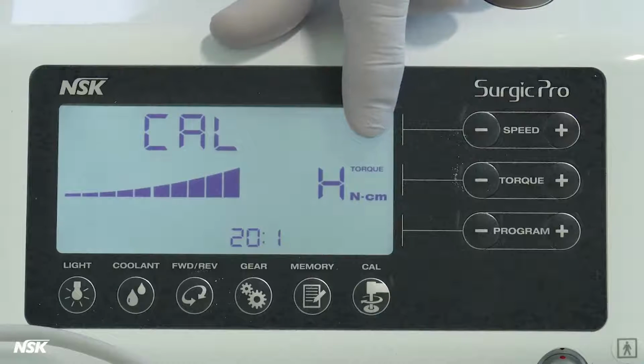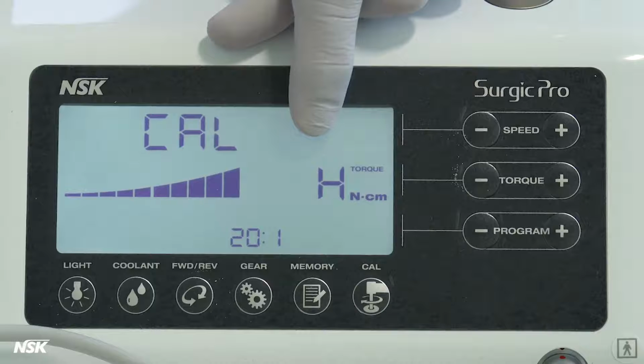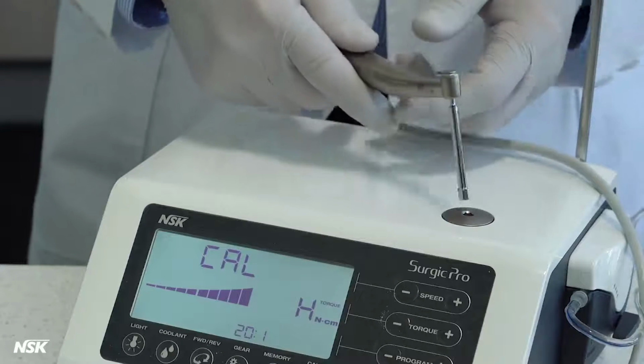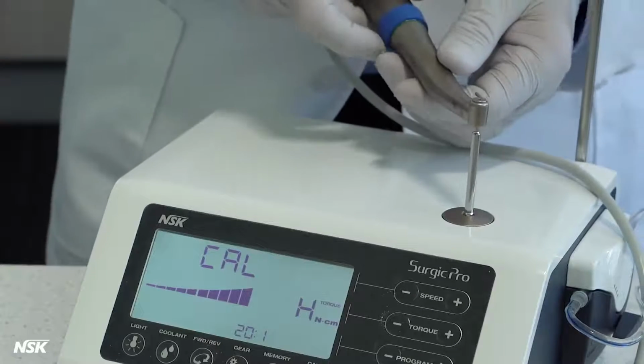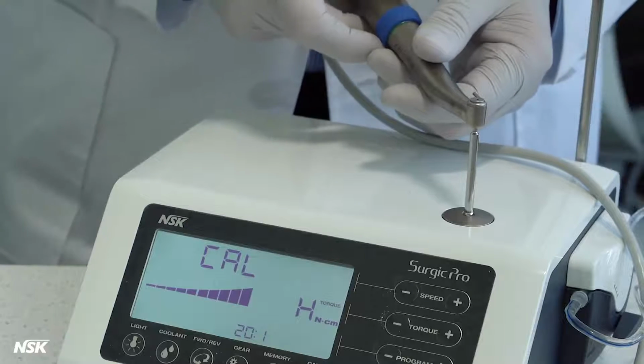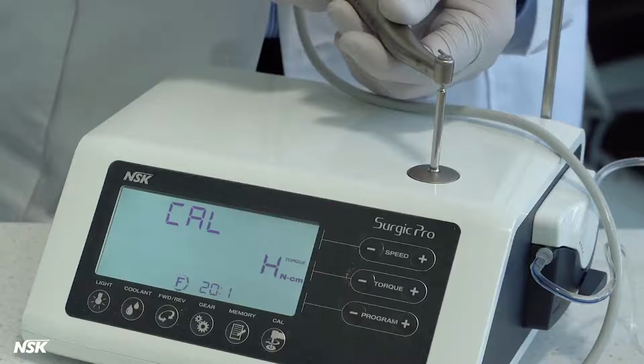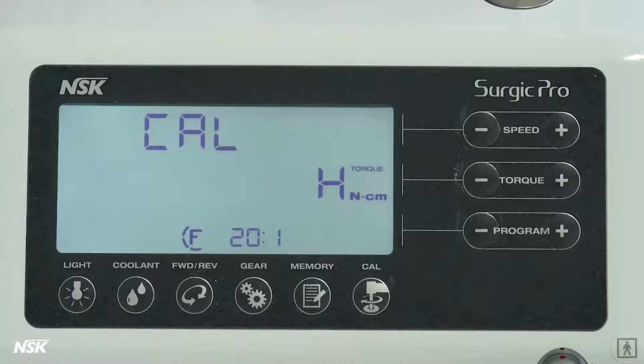Step 2. Load calibration. Torque display changes to H now. Insert the hexagon head of the drill into the calibration block. Hold the motor tightly so it cannot move left or right. Press the Cal key. The drill will begin to rotate the round block rather heavily. Once this part is completed, you will hear a beep and see Done on the display.